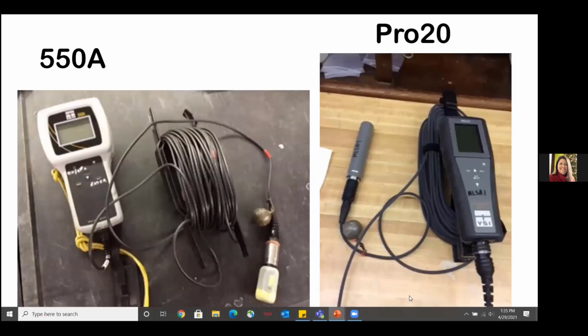So here's just another view of the 2 meters. The 550A, here's the cable, and it comes wound on the spool to keep it organized and keep the knots out of it. It has a weight on it to weigh it down so it goes straight into the water column. And then this is the probe at the end with a plastic cover on it to protect it. With the Pro 20s, the probe is a little longer, it looks a little different. A lot of them don't have the weight on them because this itself is much heavier than with the 550As, but they still come with a cord that's wound around a spool.